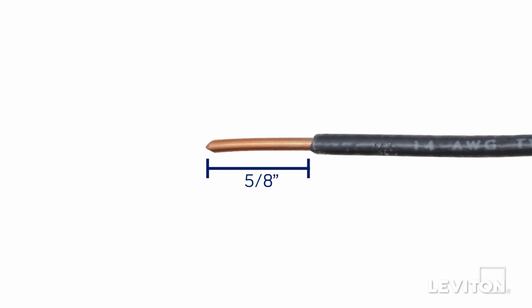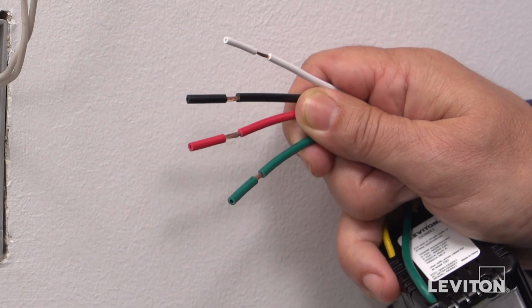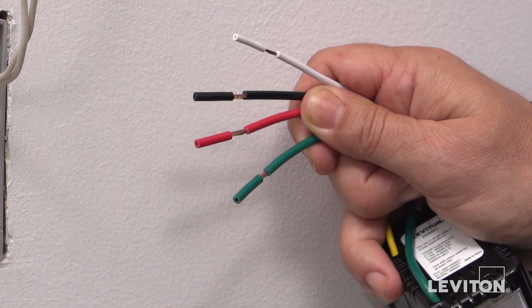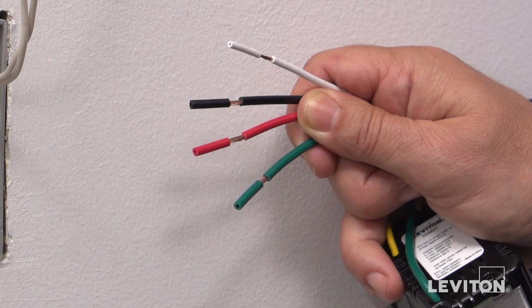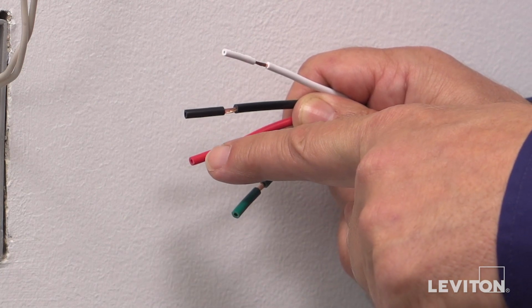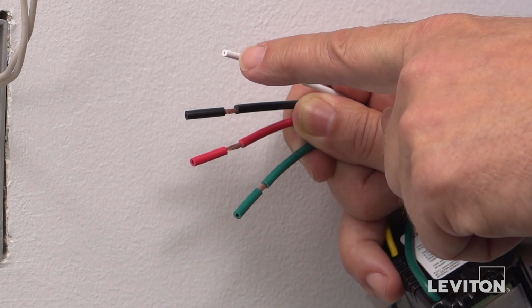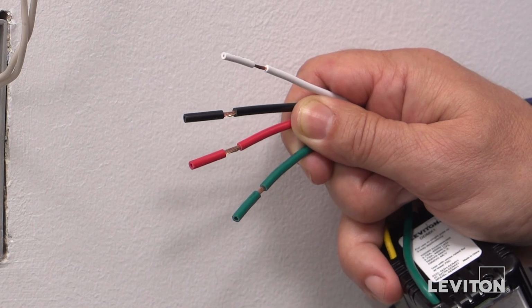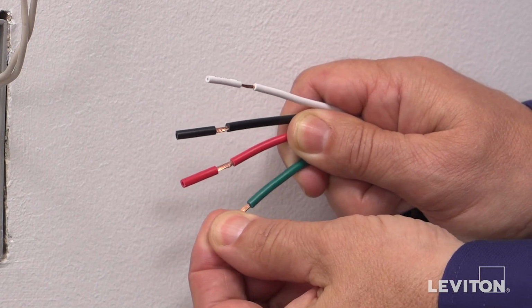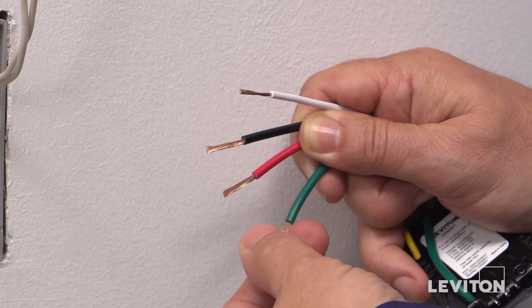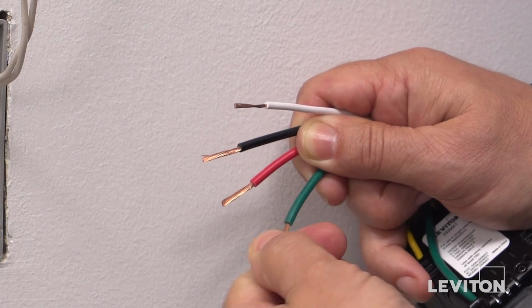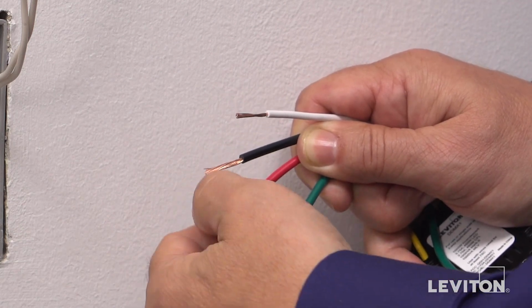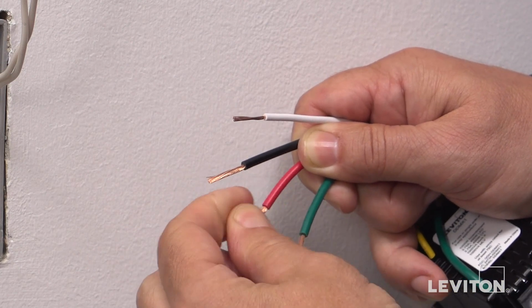Next, make sure that the ends of the wires from the wall box are straight and stripped approximately 5/8 of an inch. If not, you may need to cut them. The ends of the wires on the device have been prepared so that a small piece of insulation can be easily removed and expose the correct amount of conductor needed for terminating. With your fingers, pull firmly on this insulation to remove the pre-stripped section. Next, twist the exposed stranded copper wiring in a clockwise direction in order to prepare it to be terminated.